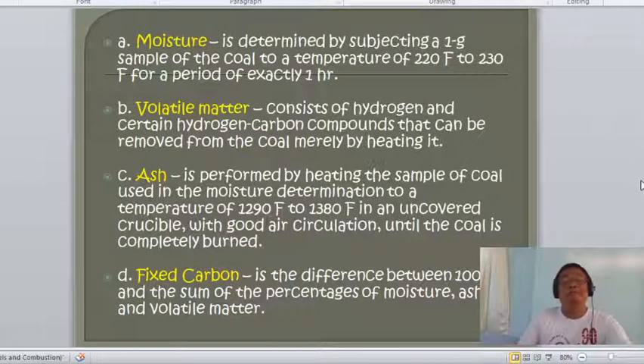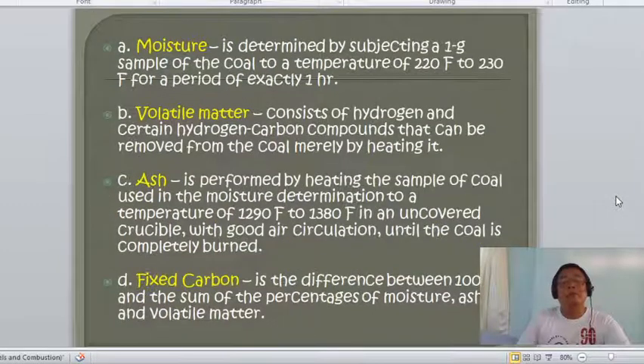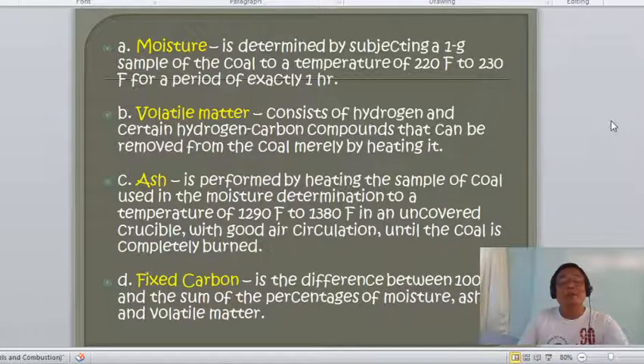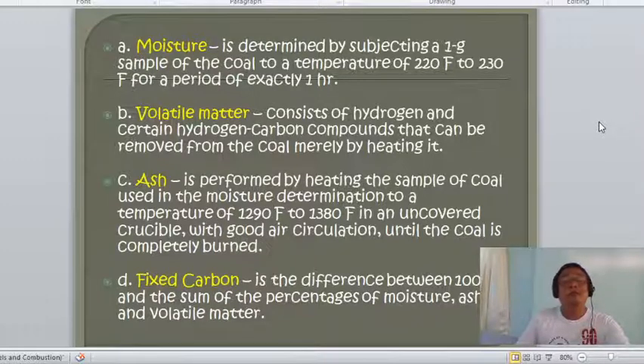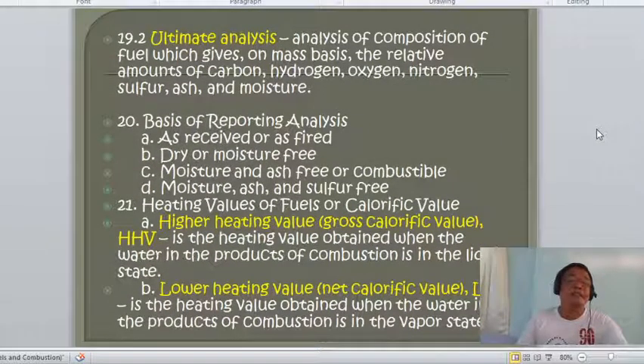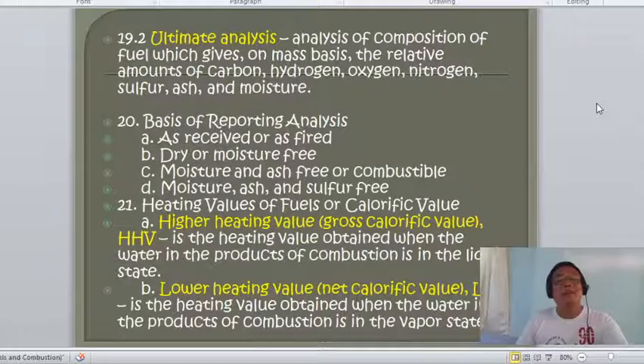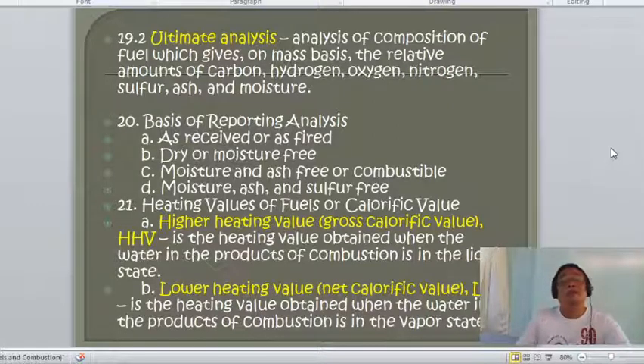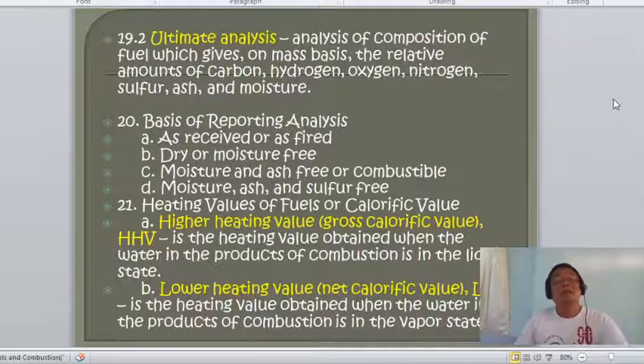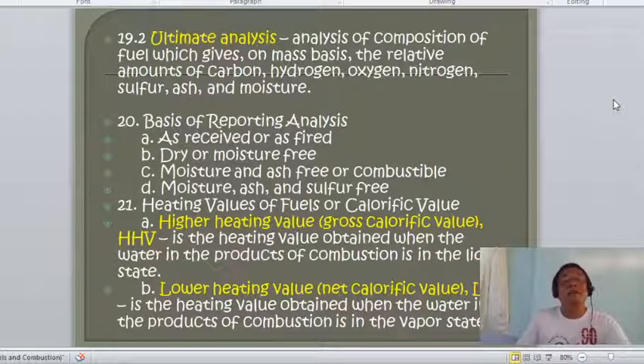Fixed carbon is determined by difference: 100% minus the sum of the percentages of moisture, ash, and volatile matter. The ultimate analysis defines everything about the composition of fuel — on a mass basis, it gives the relative amounts of carbon, hydrogen, oxygen, nitrogen, sulfur, ash, and moisture, covering all elements involved in the fuel.